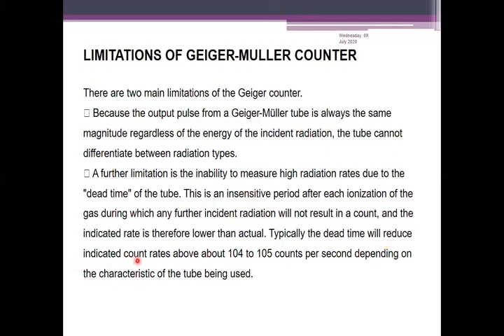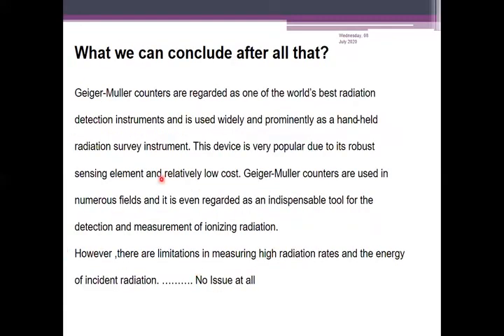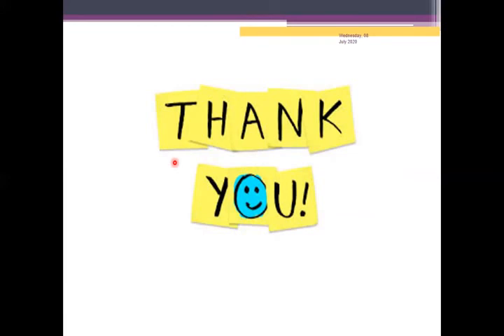In conclusion, Geiger-Müller counters are regarded as one of the best radiation detection instruments and are used widely as handheld radiation survey meters. This device is very popular due to its robust sensing element and relatively low cost. Geiger-Müller counters are used in numerous fields and are regarded as an indispensable tool for the detection and measurement of ionizing radiation. However, there are limitations in measuring high radiation rates and the energy of incident radiation. In the next lecture, we will study about the dose calibrator, which is another type of gas-filled detector for the determination of ionizing radiation counts.